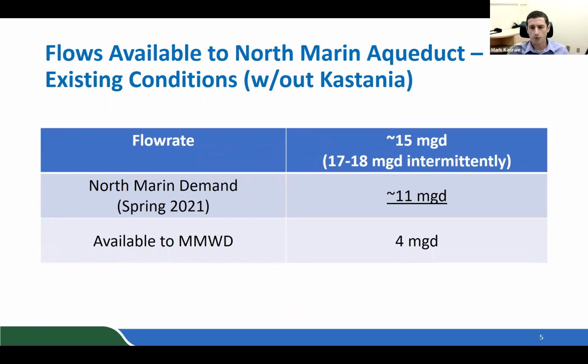During the design phase of this project, we modeled the hydraulics for the North Marin Aqueduct, and we looked at both with and without Kastania pump station in operation. This slide shows that the water flows available to the district earlier this spring, when North Marin was filling Stafford Lake, provided about 15 million gallons per day. Again, this is without Kastania pump station in operation. North Marin's demand was about 11 million gallons per day, which left about 4 MGD to Marin Water.